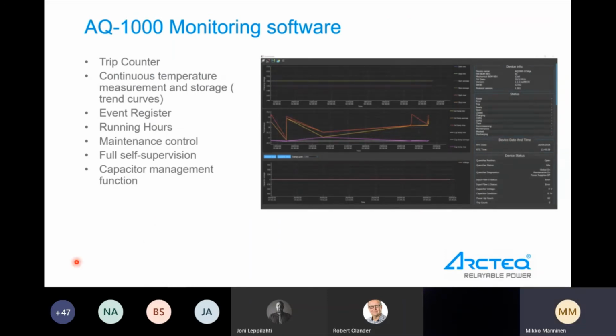Then for this unit, we have special monitoring software, which has a trip counter, temperature measurement, and event registers. We can see running hours. And for example, it is good to know the capacitor management function. The capacitor is actually charged and recharged constantly. It is not good for the capacitor inside to always be at a very stable level, and that's why we are recharging and charging it in a cycle.